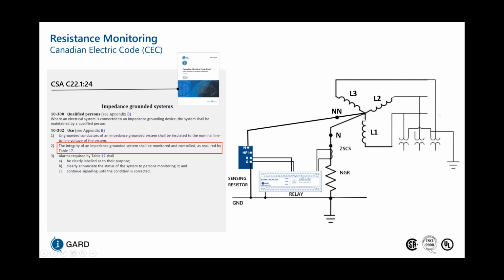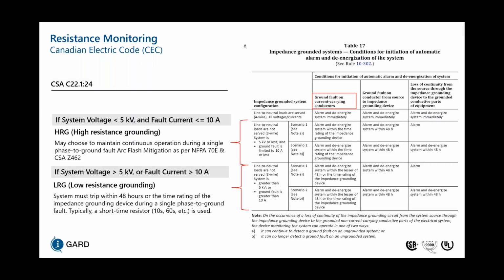Now, with the high frequency AC injection, once we reach this XO point, the high frequency forces this inductance path to be of higher impedance than the NGR because of 2 pi FL. So with F being really high, we now have the majority of the signal going down through the NGR to be reconfirmed at the relay. And that's how we were able to do the resistor monitoring aspect.